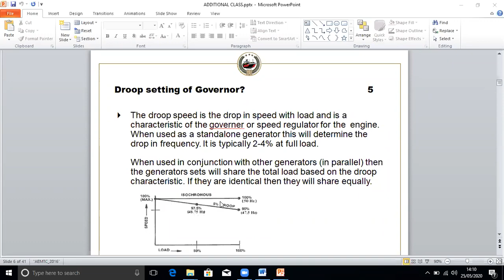So the load sharing can be anywhere, so it will be an unstable load sharing. Isochronous means there are no droop settings and the frequency is identical everywhere, so it will be unstable if you use isochronous for parallel running. Isochronous means there is no droop. You can see the second one: this is having a droop. So this is with droop, and this is without droop.